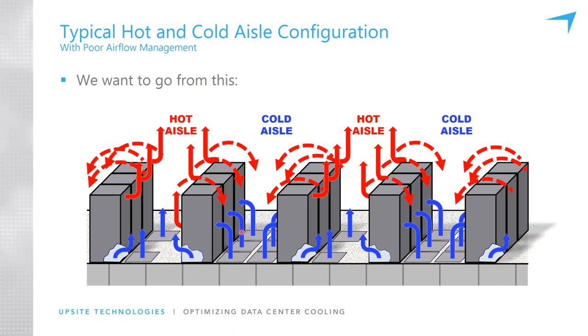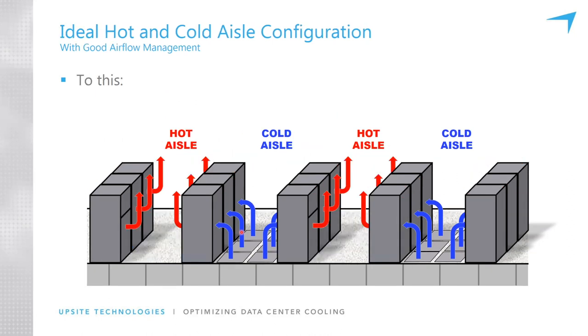So containment gives us the ability to improve airflow management to the degree that we can now optimize the space and be much more efficient. And this is the way we really want it to look. We want only cold air to be in the cold aisle, that conditioned air, and actually not very cold. In a modern efficient data center, the cold air is actually around 75 to 80 degrees, not very cold. And the hot aisle, though, is very aptly named. The hot aisle in a very efficient data center might be 100, 110 degrees, a very hot environment. So this is the way we want it to be, full separation of cold and hot air.